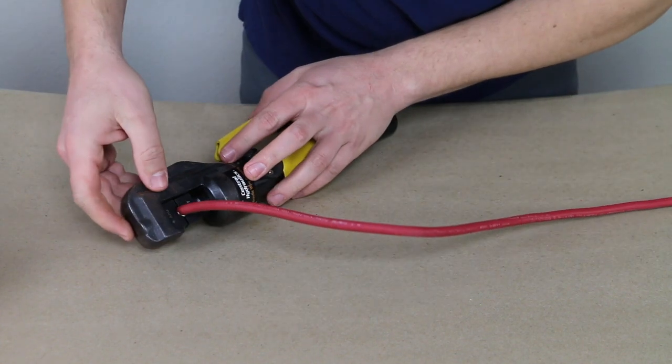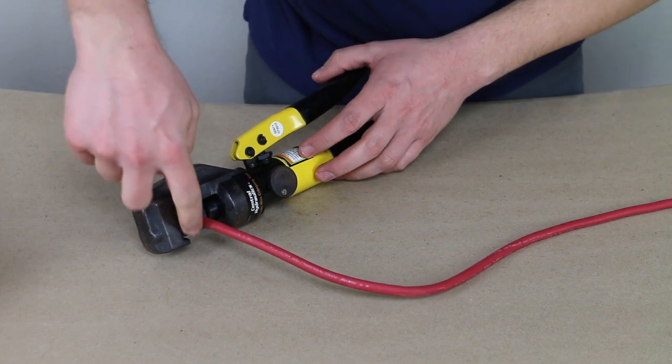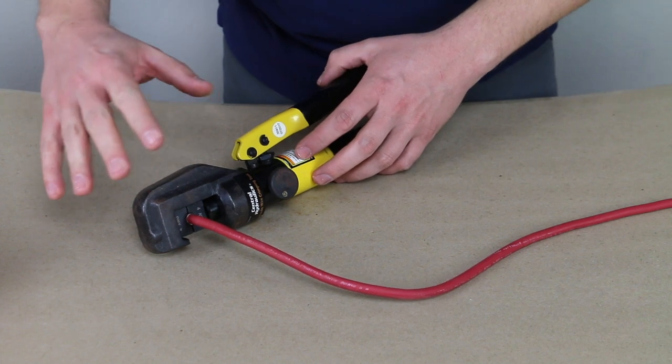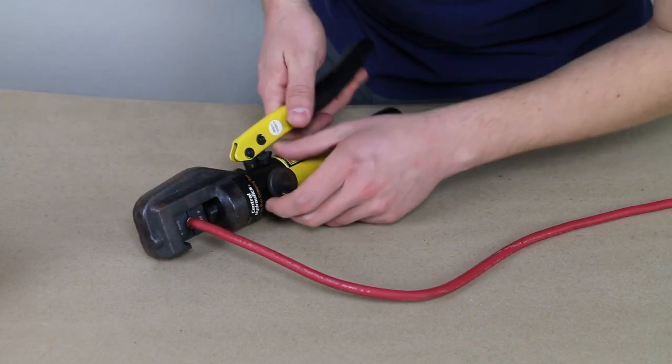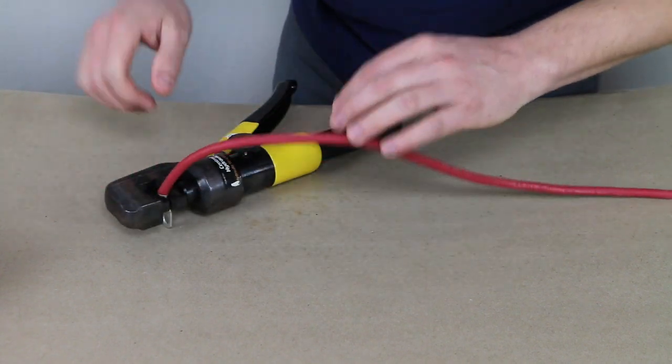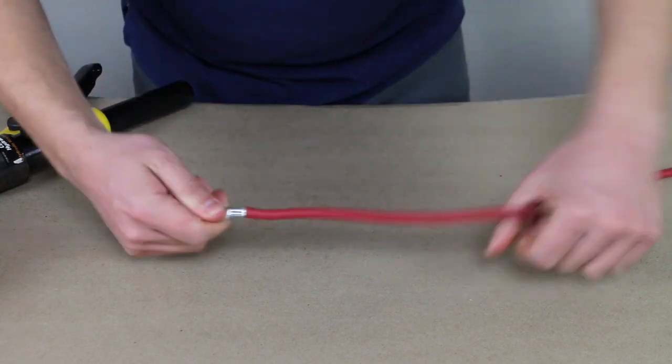Now you don't have to crush these all the way down until the jaws close, especially if you are using different size dies. Sometimes it's a little bit of an art, but if you go all the way, sometimes it can kind of squish the metal out and we don't want to do that. So that is a pretty good crimp.